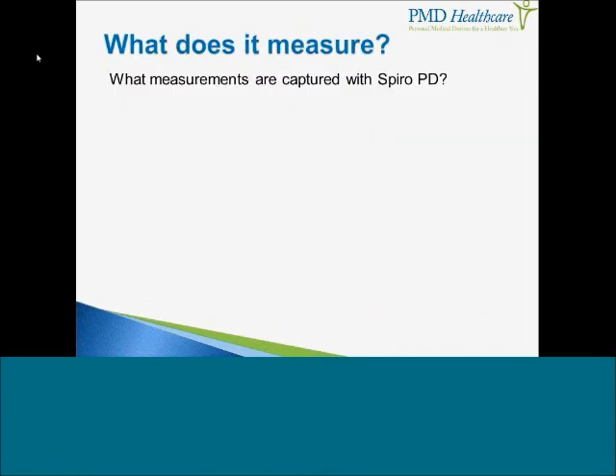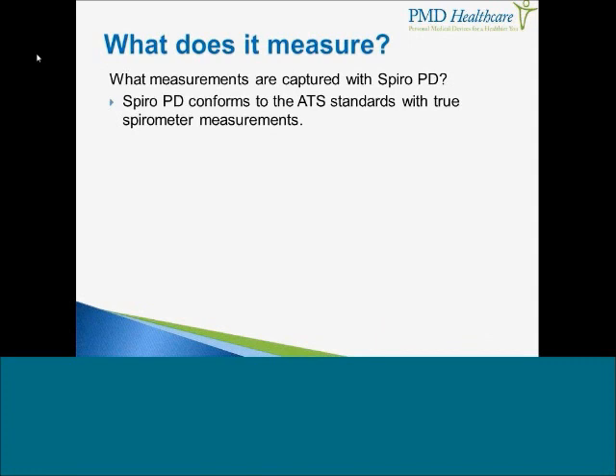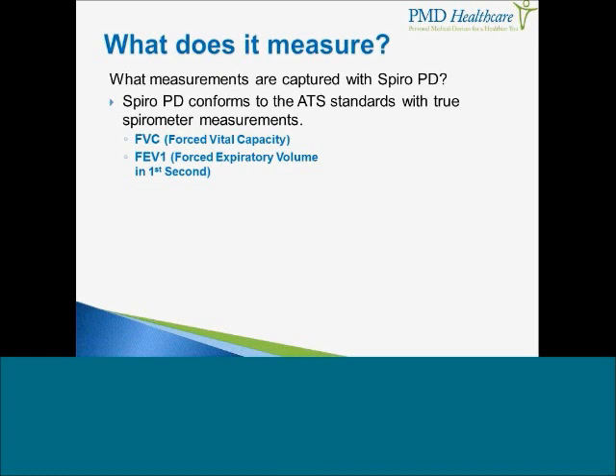SpiroPD captures several different measurements and they all conform to the American Thoracic Society standards. It measures FVC, which stands for Forced Vital Capacity — the total amount of air that you can expel from your lungs after you take a deep breath. It measures FEV1, which is forced expiratory volume in the first second — that's how much air you can expel from your lungs just within the first second of your breath. It also measures FEV1/FVC, the ratio between the two, comparing how much air you've breathed out in total with how much air you've expelled in just that first second.